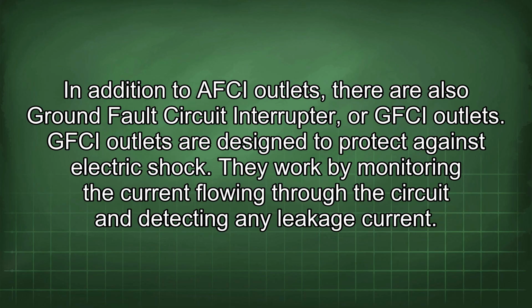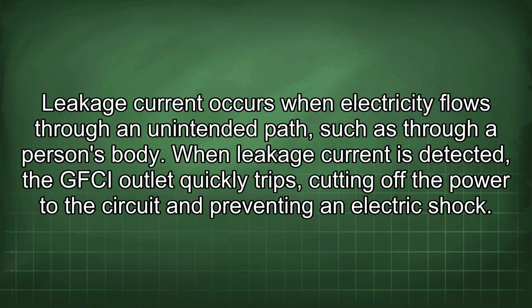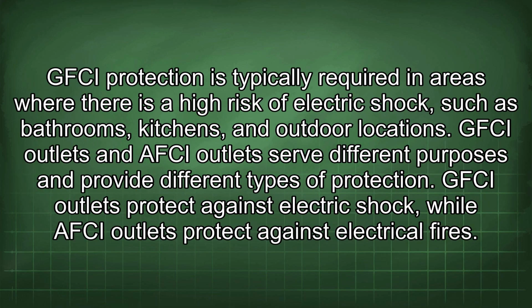In addition to AFCI outlets, there are also ground fault circuit interrupter, or GFCI outlets. GFCI outlets are designed to protect against electric shock. They work by monitoring the current flowing through the circuit and detecting any leakage current. Leakage current occurs when electricity flows through an unintended path, such as through a person's body. When leakage current is detected, the GFCI outlet quickly trips, cutting off the power to the circuit and preventing an electric shock. GFCI protection is typically required in areas where there is a high risk of electric shock, such as bathrooms, kitchens, and outdoor locations.